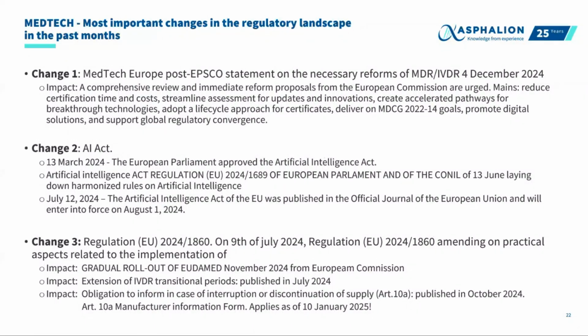The second change is about the Artificial Intelligence Act. The European Artificial Intelligence Act established rules for the development, market placement, and use of artificial intelligence systems in Europe, focusing on a risk-based approach. The Act obligates artificial intelligence providers to ensure safety and rights protection throughout the artificial intelligence system's life cycle, with a European Artificial Intelligence Board. It is important to highlight that the Act entered into force on August 1st, 2024. It means that the Act became part of the legal system of Europe on August 1st, 2024. So after this date, the Act is legally applicable, but this date is not a deadline for manufacturers.